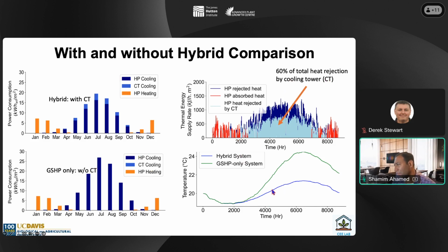This is the conventional ground source heat pump. You can see the ground temperature increases, and it could go up to 24 degrees Celsius. If it increases year by year, it could reach a level where the ground source heat pump will not work anymore. But with a hybrid system using cooling towers, the ground temperature fluctuation is much smaller, only 1 to 2 degrees Celsius, balanced out over the year.